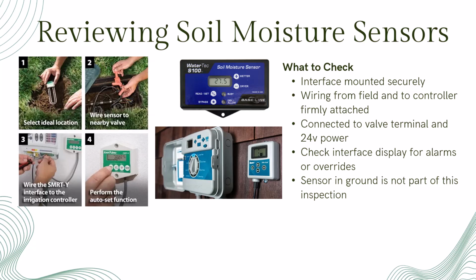I start by confirming the interface is mounted securely and that all wiring is tight. Since these devices piggyback on a valve wire, there should be a clean connection from the field into the interface and then from the interface back to the controller's valve terminal, with 24-volt power tied in as well. Finally, I check the display for alarms, error messages, or override settings that could prevent the sensor from doing its job.